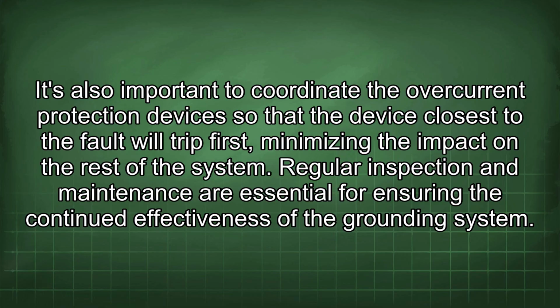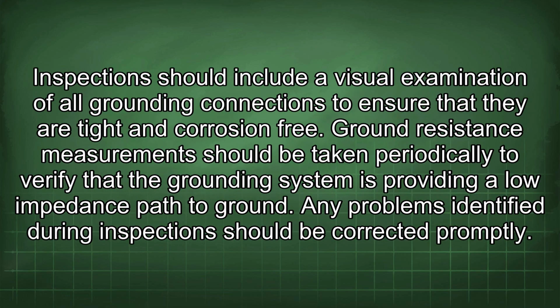Regular inspection and maintenance are essential for ensuring the continued effectiveness of the grounding system. Inspection should include a visual examination of all grounding connections to ensure that they are tight and corrosion-free. Ground resistance measurement should be taken periodically to verify that the grounding system is providing a low impedance path to ground. Any problems identified during inspections should be corrected promptly.